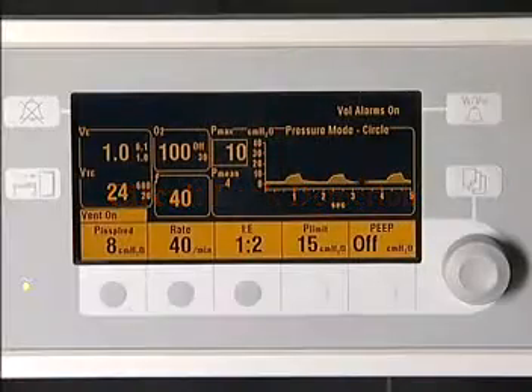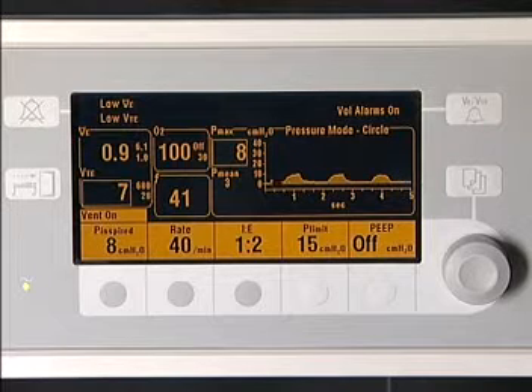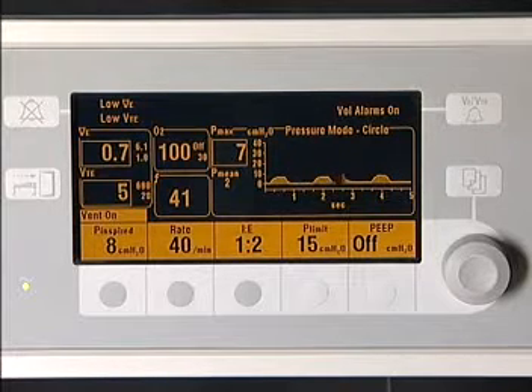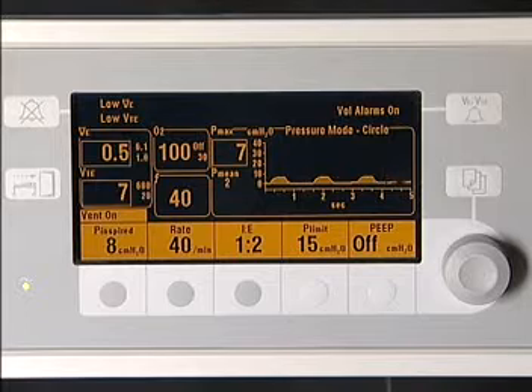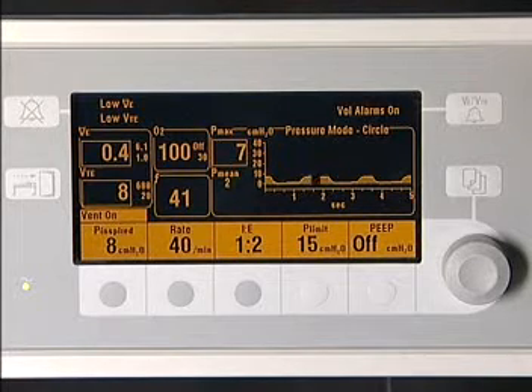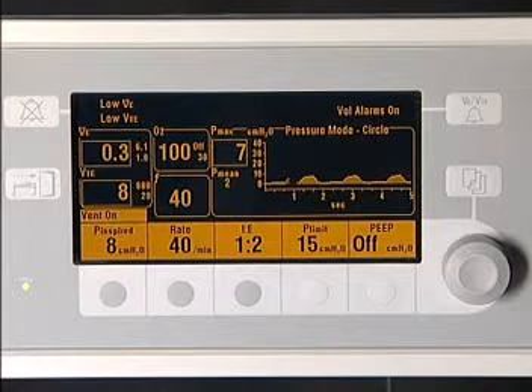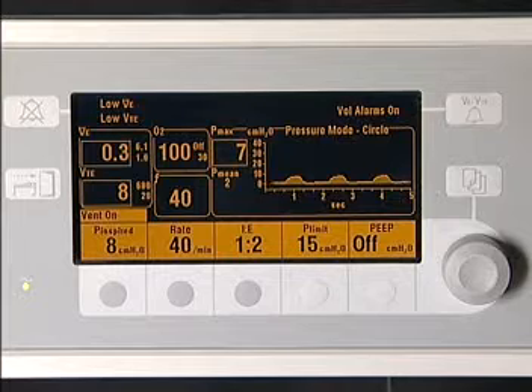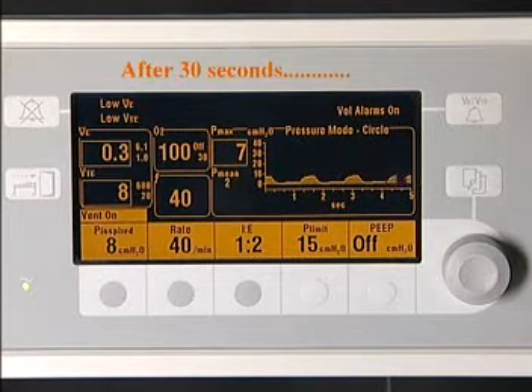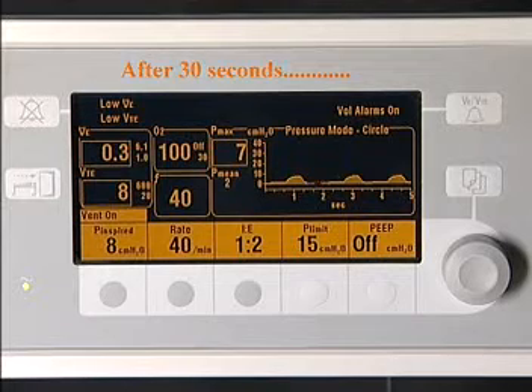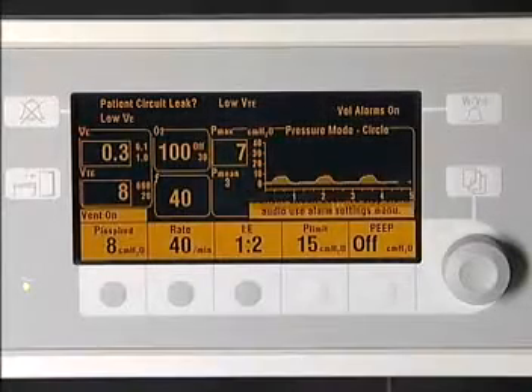The Aestiva does not provide a fixed volume algorithm to determine potential disconnects. This is necessary because volumes below 20 ml are possible in the pressure control ventilation mode. Instead, the Aestiva looks for at least 50% of the inspired volume to be returned to the exhalation sensor. If less than 50% is returned, a message, circuit leak?, is posted with an alarm tone to warn of a potential partial disconnect.